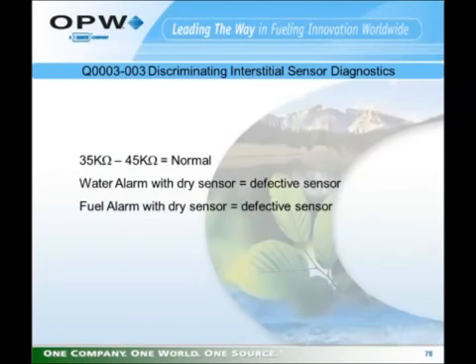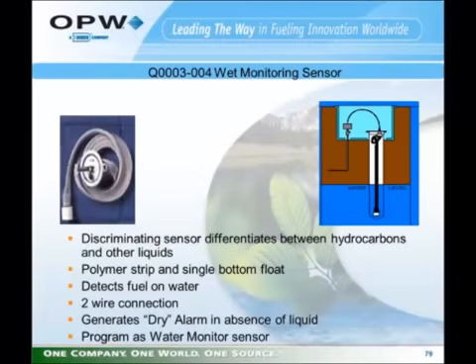The normal resistance reading on this unit is given here, 35 k ohms to 45 k ohms. If you have a water alarm or a fuel alarm and the sensor is dry, that is indicative of a defective sensor. That is if the sensor is connected directly to the tank gauge for testing purposes only. Keep in mind that these sensors work off of a resistance that changes with different conditions. If your field wiring resistance comes into play, then defective field wiring can cause false sensor alarms if the resistance readings at the sensor interface connections at the tank gauge indicate what might be an alarm condition at the sensor itself.